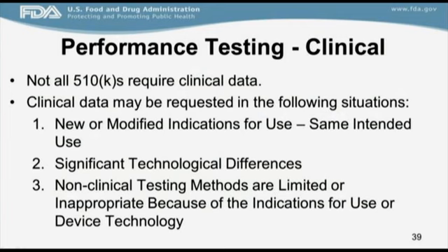When you have new or modified indications for use, clinical testing may be needed. If you're making significant technological changes, that may also require new clinical data. Or when non-clinical testing methods are limited or inappropriate because of the indications for use or device technology. Please refer to the 510K program final guidance for additional examples and explanation on when clinical data may be appropriate.